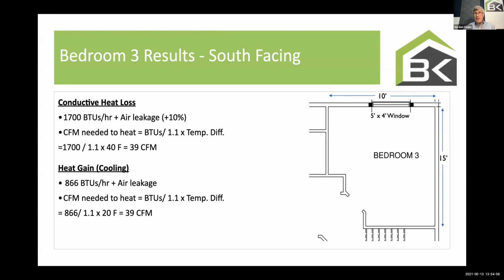So how much air do I need to heat that room? I need 1,700 BTUs divided by 1.1 and divided by 40. I need 39 CFM. That's how many CFM I need coming out of that register on what day? On the coldest day of the year. On the coldest day of the year, I need 39 CFM.